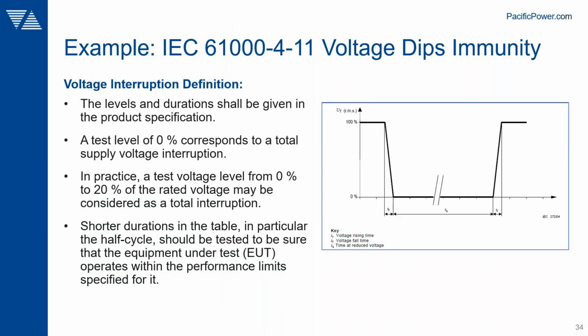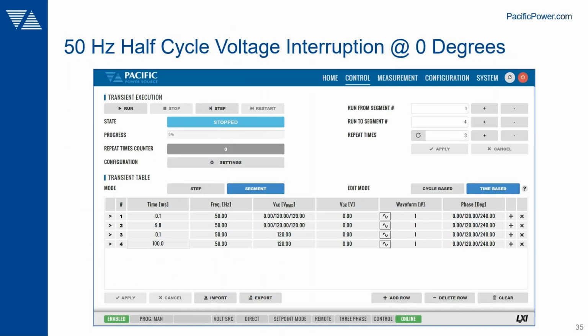Wanting to do a half cycle dip in this example, we'll use the web browser interface for convenience, since it gives us a larger screen to see what we're doing. I need just a small sequence of a couple of steps that takes the voltage from nominal down to 0 volts on phase A. As you see in the middle, I'm only stepping phase A, leaving phase B and C at the regular voltage, so I'm stepping just one of the three phases.